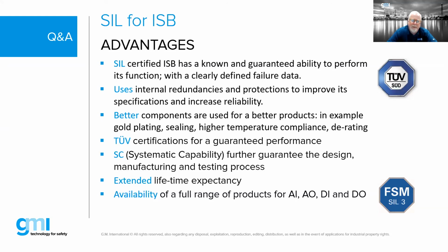Barriers do not require it. It's not a requirement that's written down within any of the 60079 standards or in the wiring regulations that I've seen. The advantage is basically the failure data rate that you've got under a SIL device: this product has been tested and certified and it is so reliable, if you will. And obviously IS is a safety critical device, so the fact that an IS barrier actually has a SIL rating is a good thing.